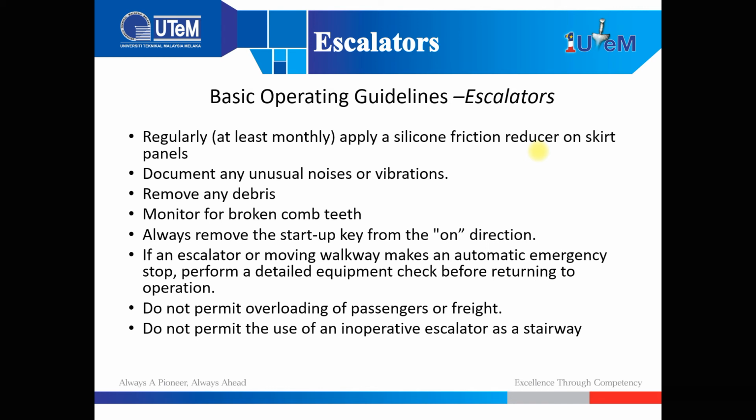So the second one is document any unusual noise or vibration. Okay, setiap noise atau vibration must be taken note of and documented. Okay, for the next, preventive maintenance. Remove any debris. Monitor for broken comb teeth. Always remove the startup key from the on direction.